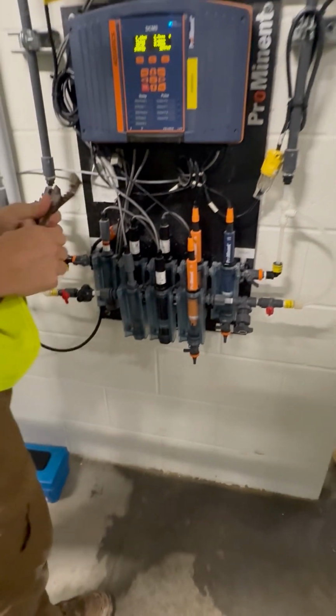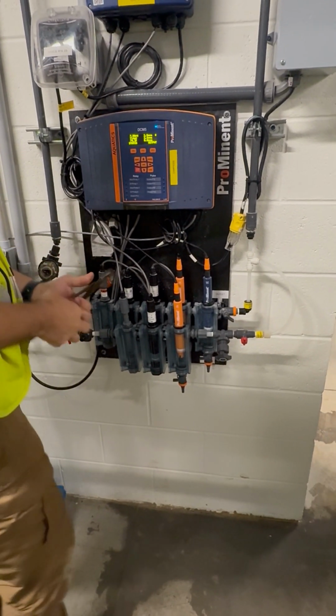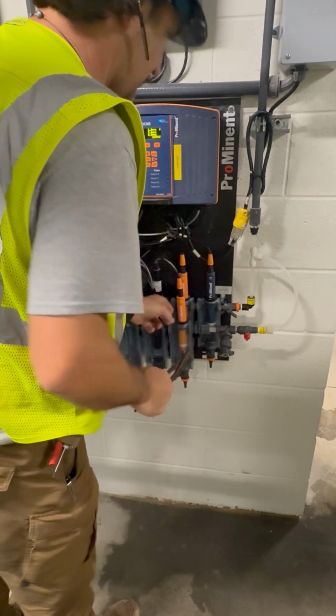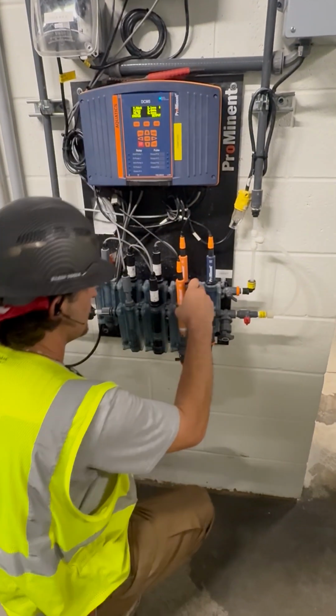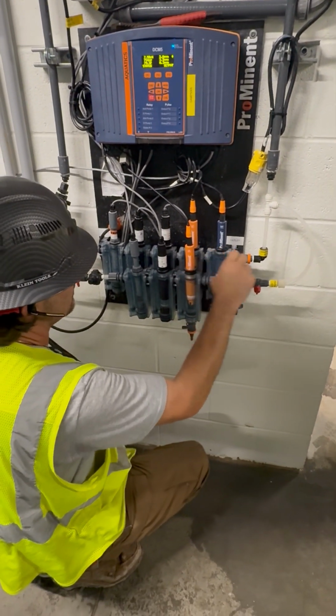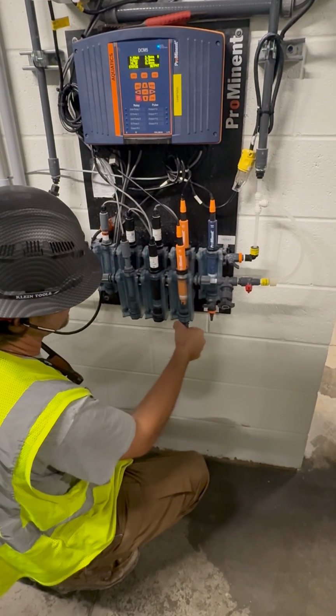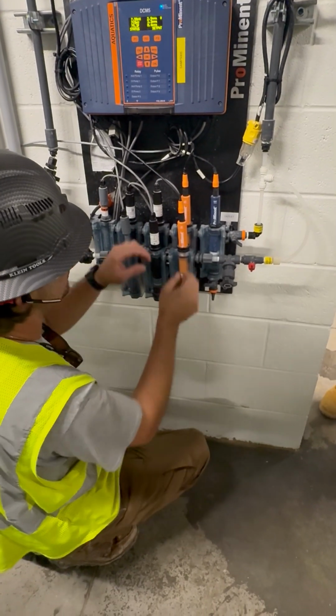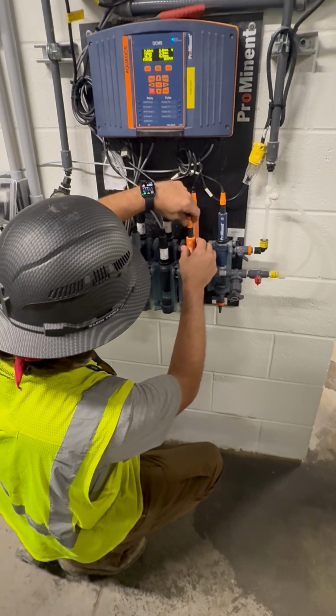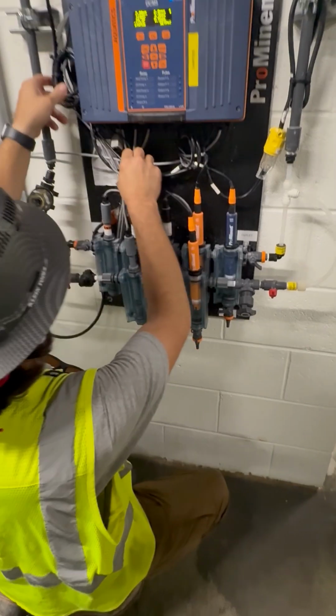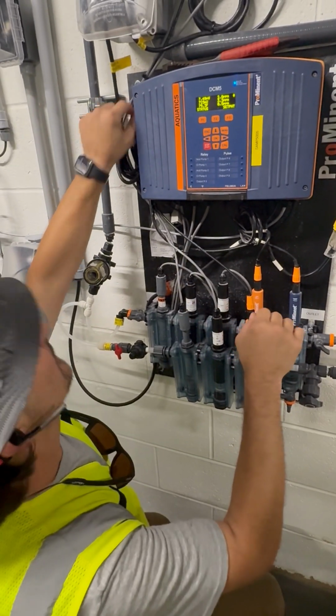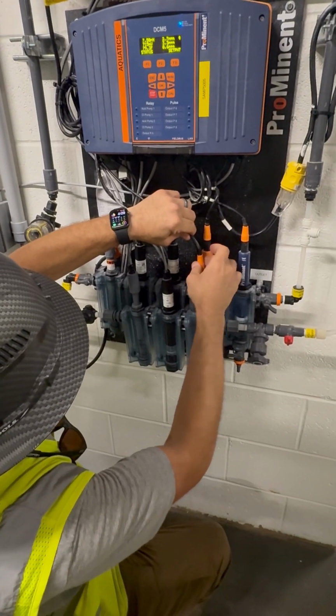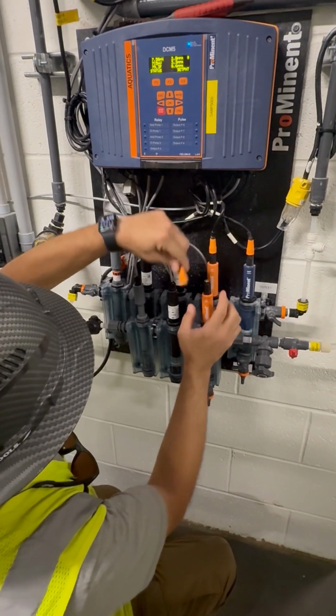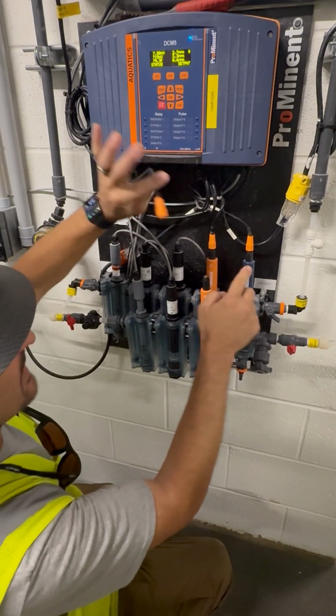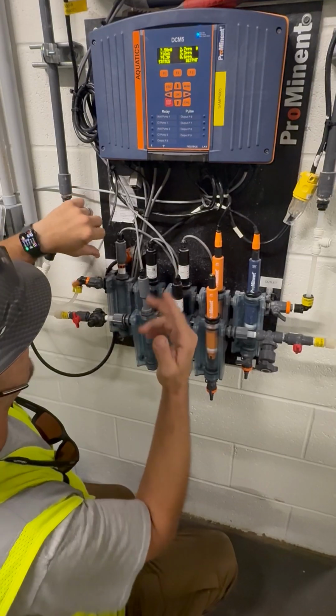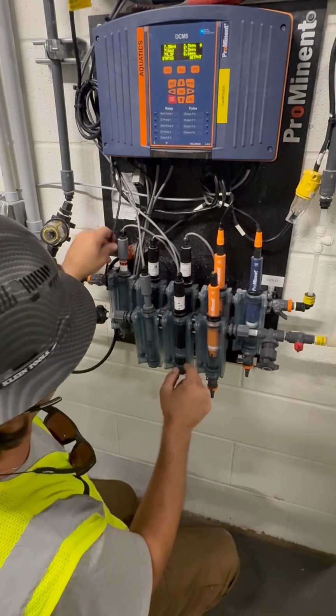You grab your channel locks and remove your nut here. Before you start pulling up on this, make sure you open this to relieve the vacuum or relieve the pressure on the system. On these guys with the orange, once you get them loose, they'll just pop right off - so this one, that one, and that one all do that. The rest of these are all hardwired in, so you can't take them off, but this one you can.